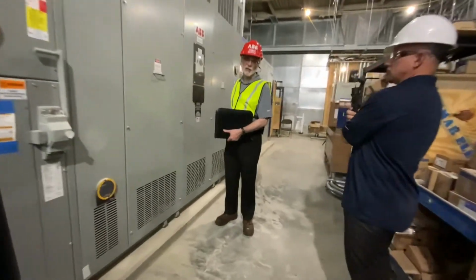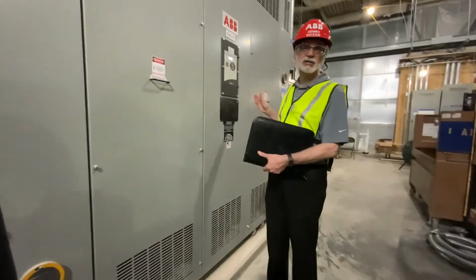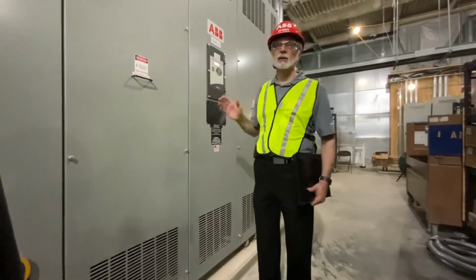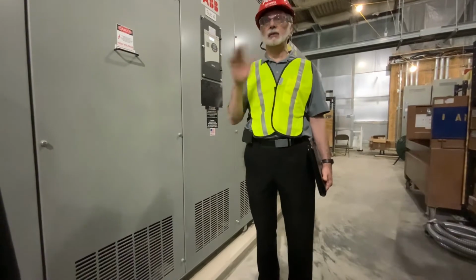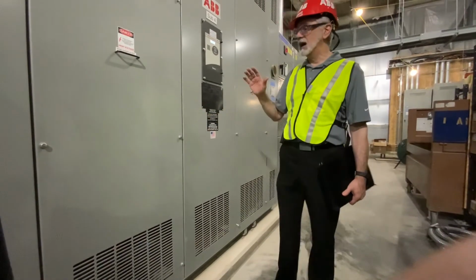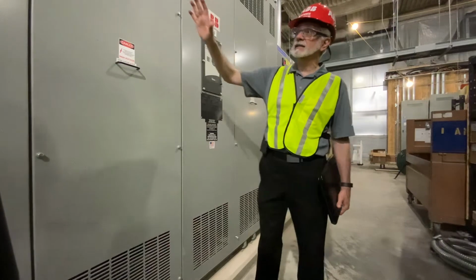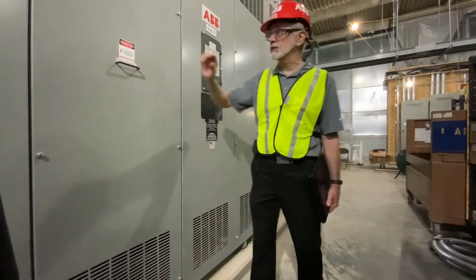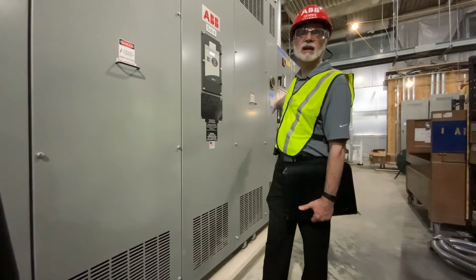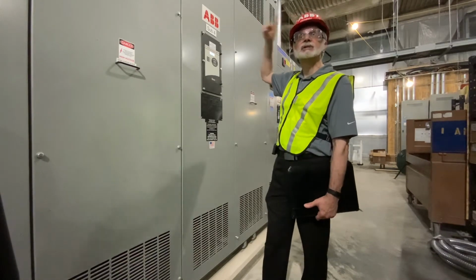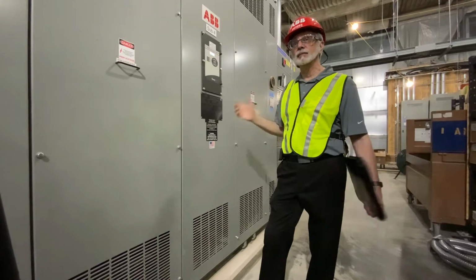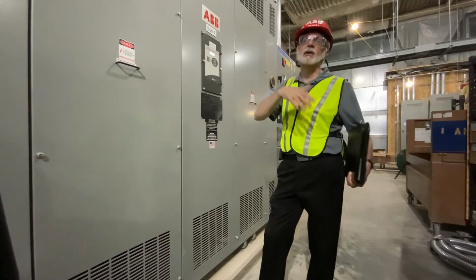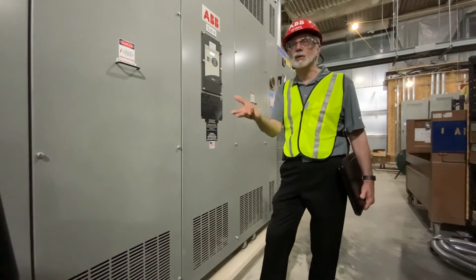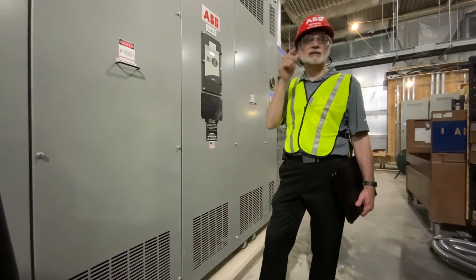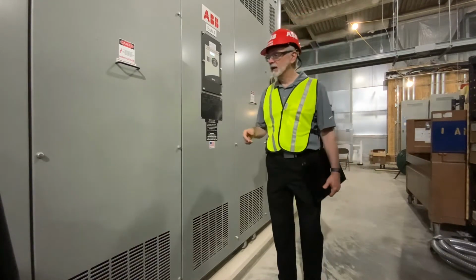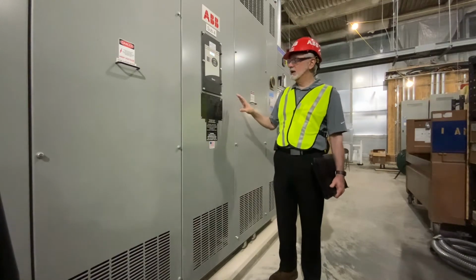Great question. Okay, we're going to move down a little bit to the next piece of equipment, which is the dry type transformer. This is a dry vacuum pressure impregnated transformer, so it's not liquid. You don't need to worry about any fluid containment or anything like that. It basically is taking the 13,200 volts and stepping it down to 277/480, which is what you're going to use to distribute electricity throughout the rest of the building. You will have other transformers that'll step it down to 120/208, but the majority of your service is going to be 277/480.